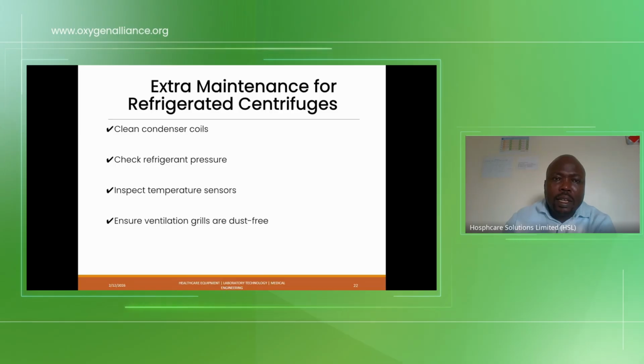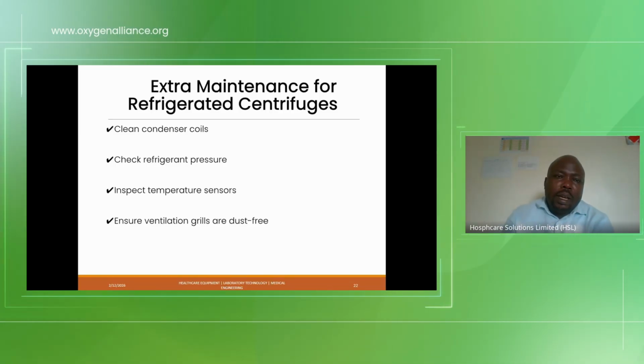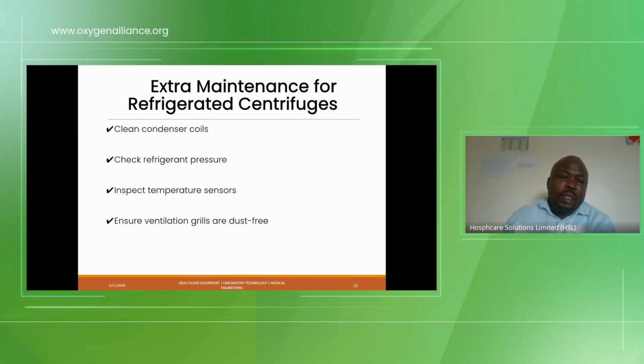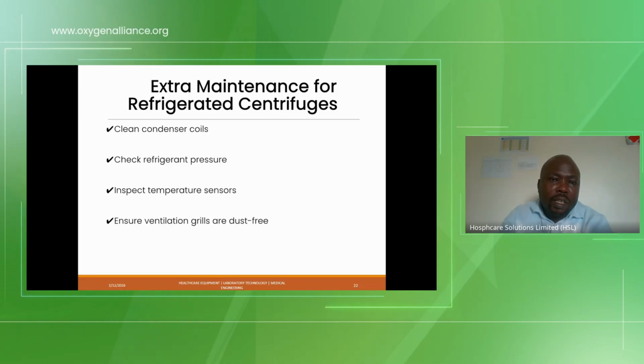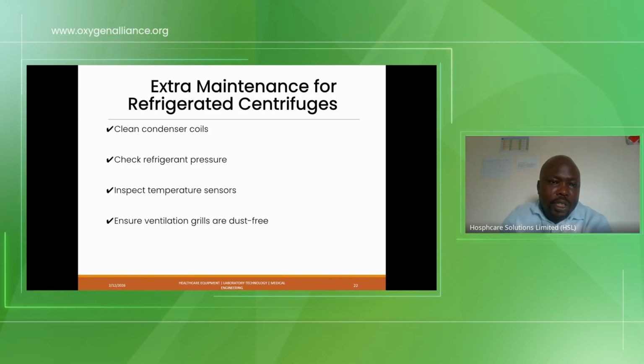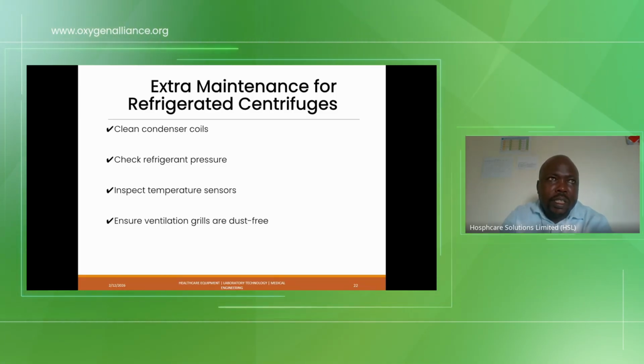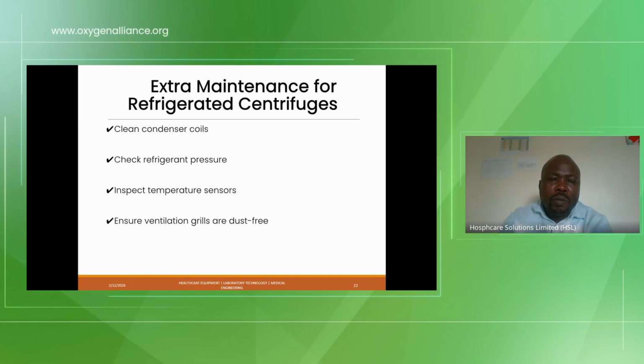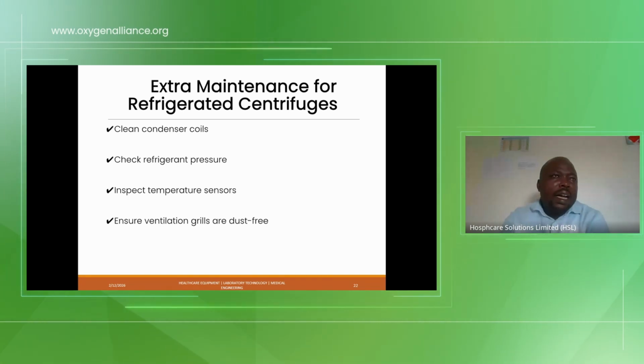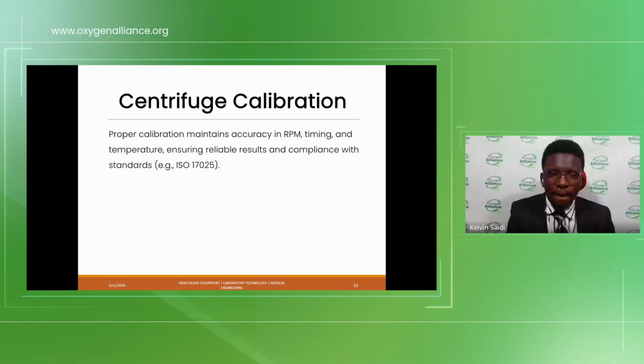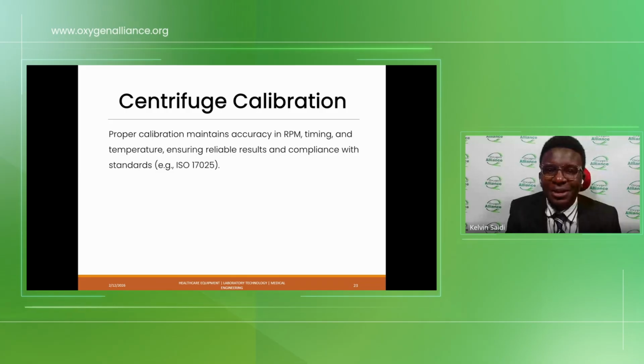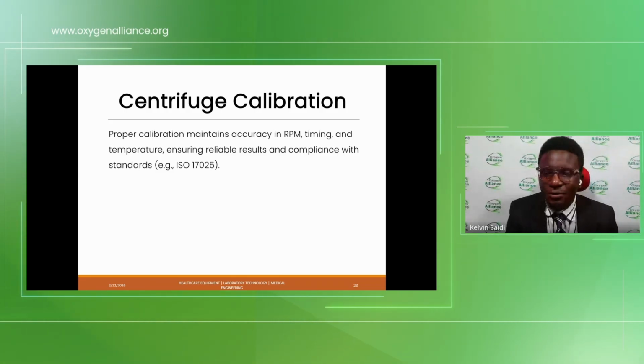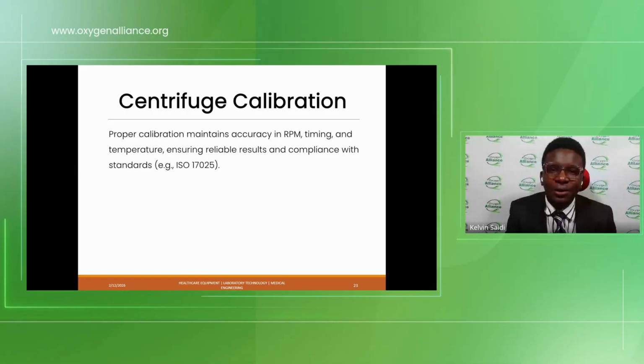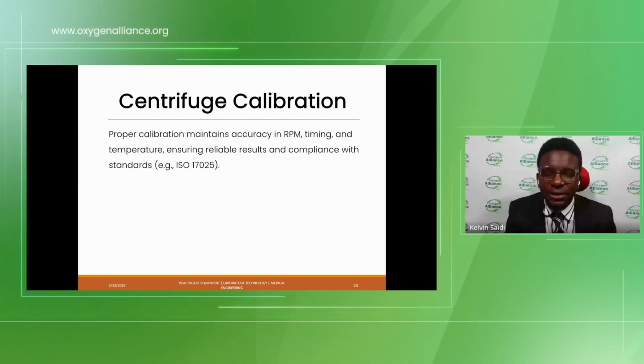Unless there is anything I need to clarify. Yeah, here is what you need to check during maintenance. You clean the condenser coil, check refrigerant pressure, inspect temperature sensors, then ensure ventilation grills are dust-free. Yeah. Right. Wonderful explanation. I don't know if Mr. Goodluck, that answers your question.